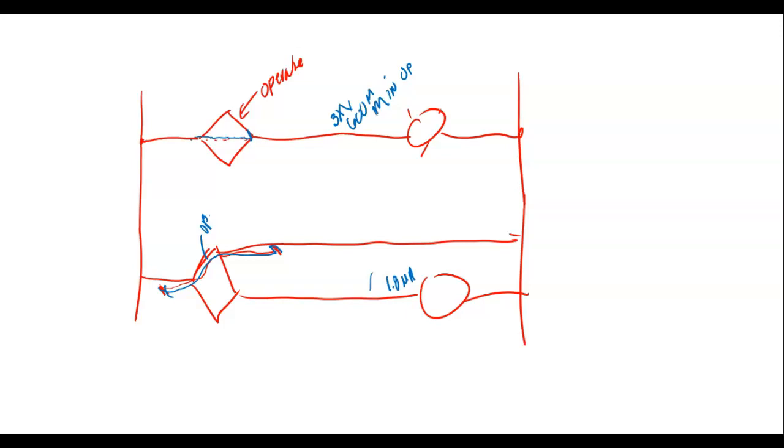631 milliamps. Not leakage current. That's milliamps. That's over half an amp. That can't be right. So that 1.8 microamps. What's that? On this one, 1.8. Not milli, micro. Oh, thank you. Yeah, 631 microamps. So the operating current is going to be in the microamps, except here, here's the operating current here, and we're not going to measure that. So this only has 1.8 microamps worth of leakage current.